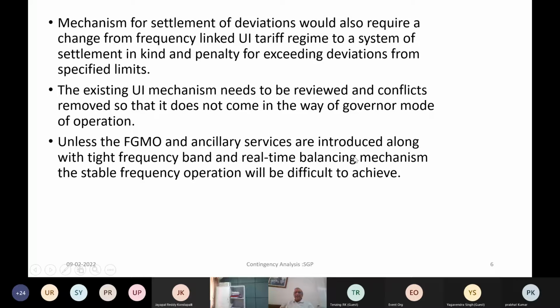Going forward, as we saw yesterday, the recommendations for IEGC 2020 are that unless FGMO and ancillary services are introduced along with the tight frequency band and a real-time balancing mechanism, stable frequency operation will be difficult to achieve. So this was a committee opinion some years back, and exactly the same thing is now being implemented. Yesterday, as we saw, free governor mode of operation along with ancillary services is being implemented. As a result of that, and also as a result of our system becoming stronger in terms of generating resources, where we now have reserve capacity online available, it is possible to implement an even narrower band. The IEGC 2020 recommends that the frequency band be tightened to 49.95 to 50.05 instead of 49.9 to 50.05.